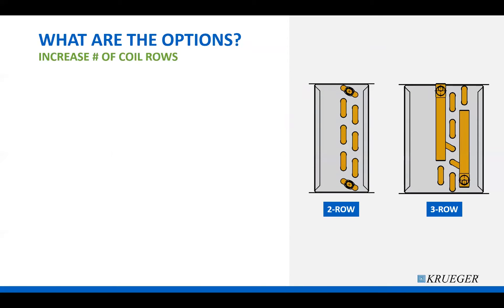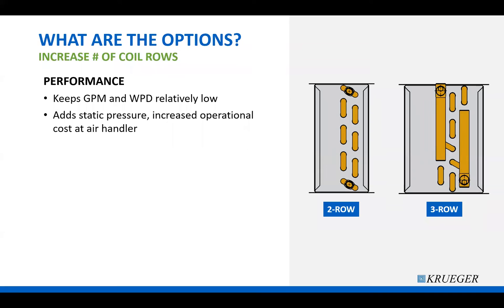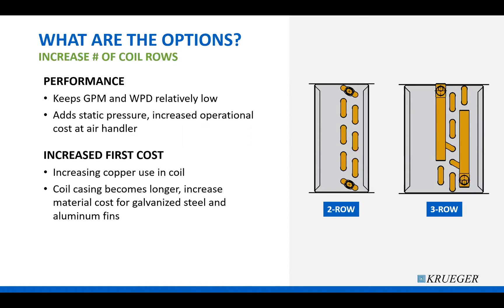So what are your options for maintaining heating capacity with lower water temperature? The first option is to increase the number of coil rows on the water coil. This keeps water flow and water pressure drop low. However, adding additional rows does add static pressure to the system because we're adding more obstructions to the air stream. This added static pressure will be seen at the air handler and can increase operating costs. Across several terminal units, you could see a requirement for larger fans and bigger motors on air handler units to compensate.